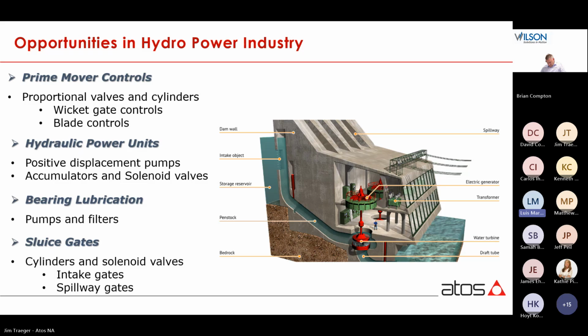Opportunities in the hydropower industry. On prime mover controls, there are proportional valves and cylinders that operate wicket gate controls and blade controls. Also, hydraulic power units install these systems with positive displacement pumps, accumulators, and solenoid valves. There is a bearing lubrication system also with pumps and filters. And for sluice gates, there are cylinders and solenoid valves that operate intake gates and spillway gates. The picture here shows some of the gates. There is a red line on the left showing the intake gate, and on top of the dam are the spillway gates, so they're right in the center. There is a turbine showing the wicket gates and blade control gates. Next slide.